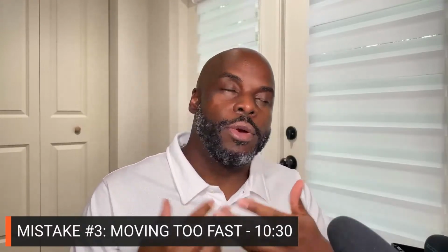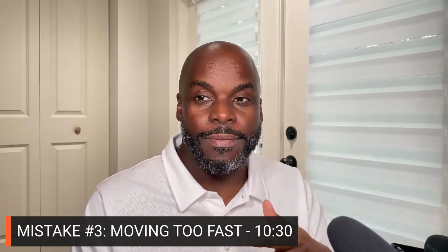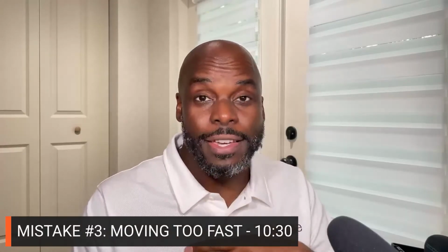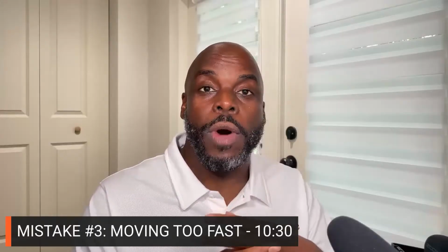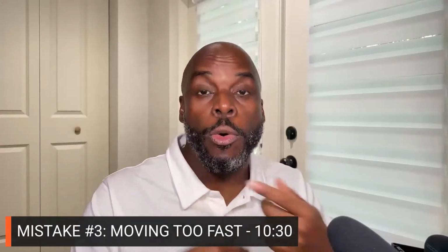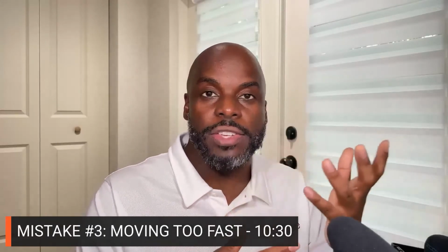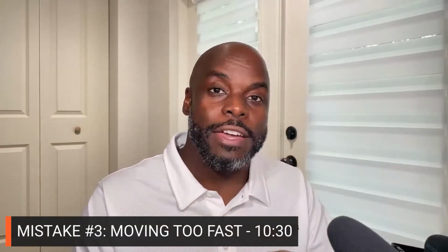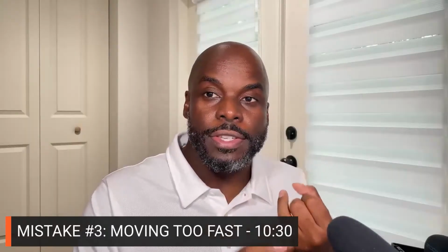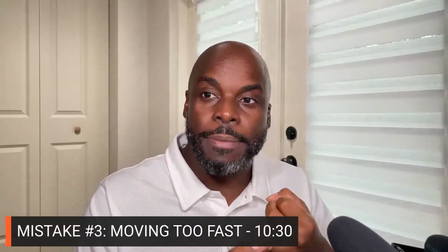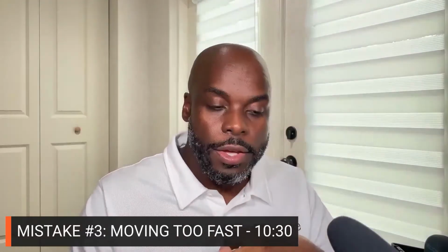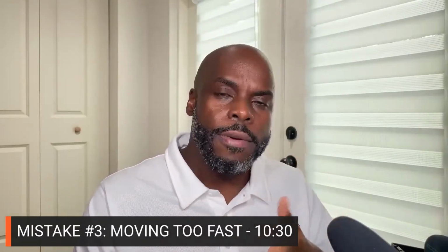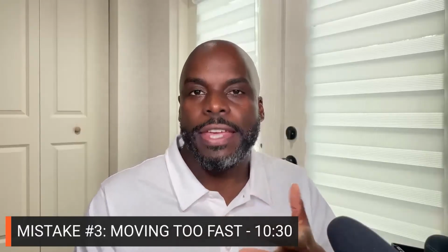Change in OT requires process. It requires change management. It requires testing, most of all. And finally, it requires plans to roll back in case the change introduces more bugs. And it requires buy-in from operations, the engineering team, and from maintenance also. So what do you do instead? First off, you slow down. At least initially, while you're learning the environment.